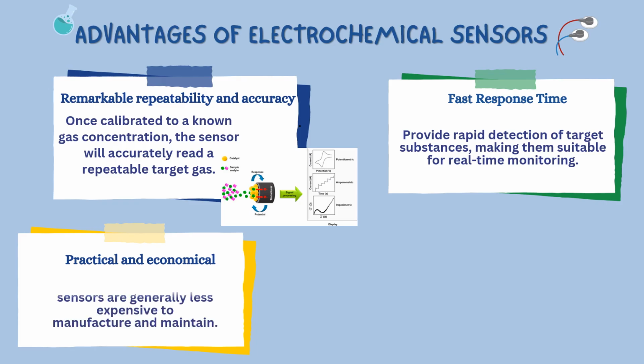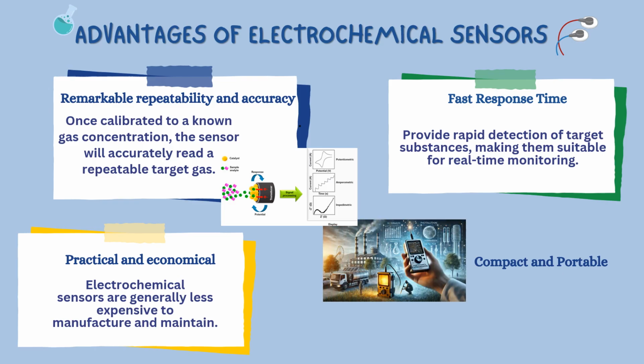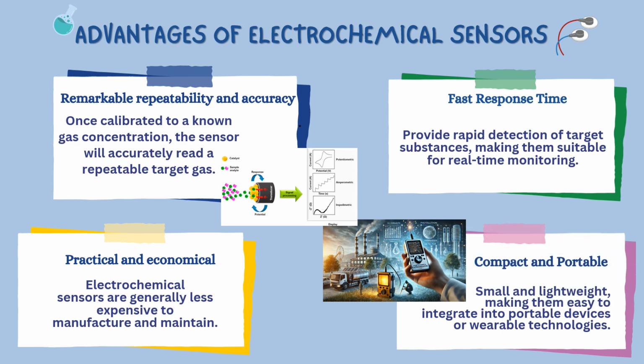The third one is practical and economical. Electrochemical sensors are generally less expensive to manufacture and maintain. Compared to the photoionization detector, PID, which can also detect the same gases as electrochemical sensors, like ammonia gas and hydrogen sulfide, PID is 3 to 5 times more expensive than the electrochemical sensors, or even more. The last advantage is compact and portable. The portability is very important because it allows easy field monitoring, rapid deployment in emergencies, and even personal safety monitoring in the workplace.